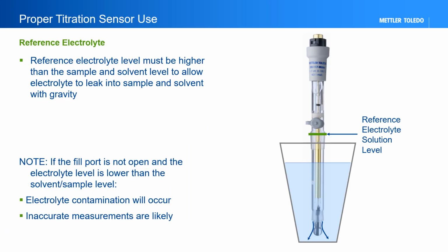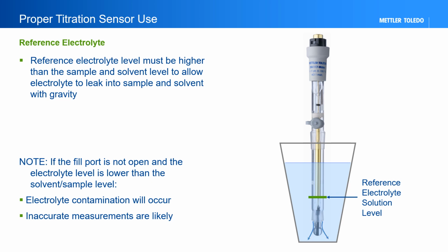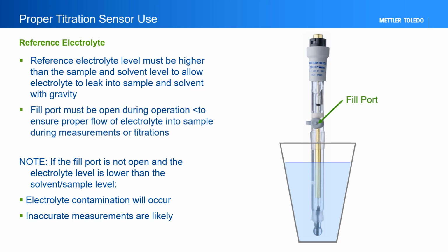One of the most important and often neglected aspects of properly using an electrode is the reference solution. The reference solution must always be higher than the sample solution. This ensures gravity will force the electrolyte to flow into the sample solution. This helps ensure accurate measurements and does not allow the sample solution to contaminate the reference electrolyte. The fill port of the electrode must also be open during use, or a low pressure environment may be created, and the reference electrolyte cannot flow into the sample solution.